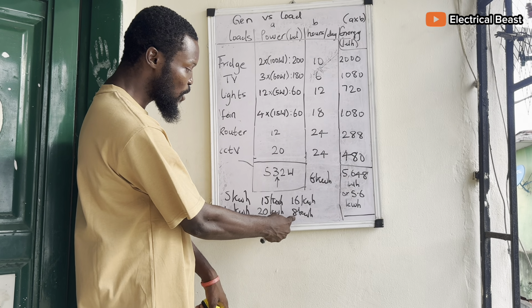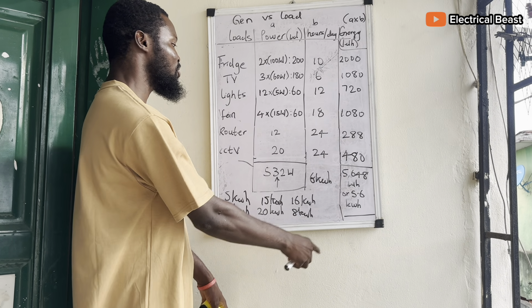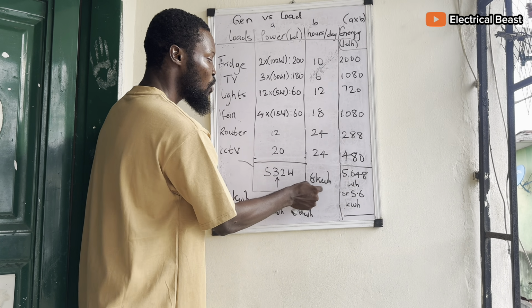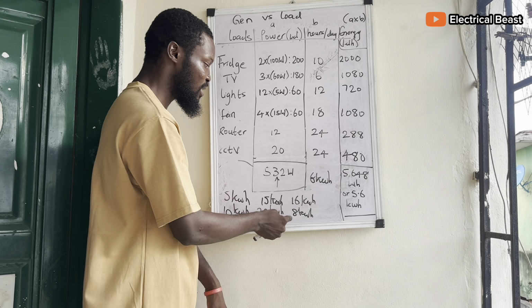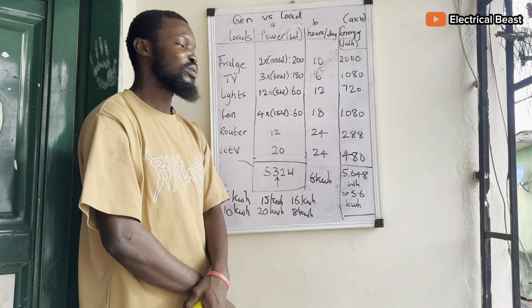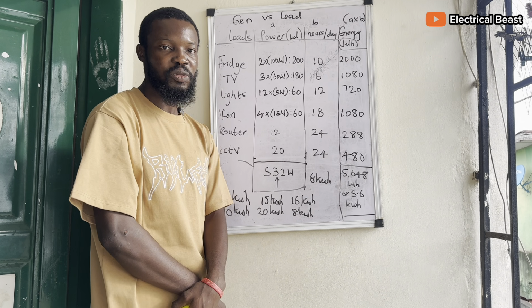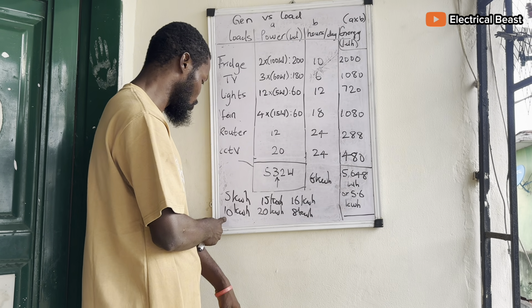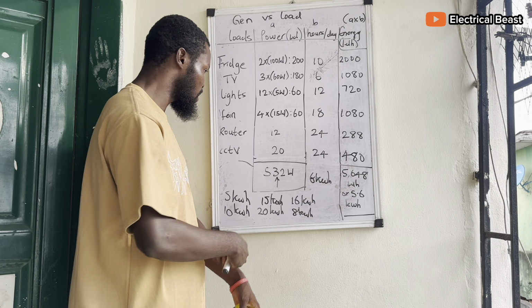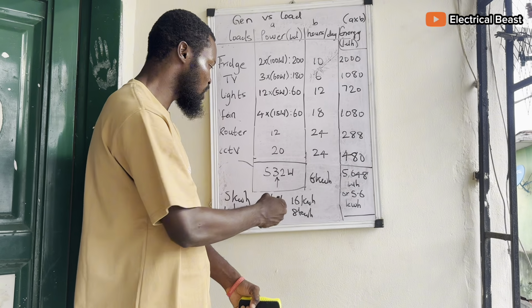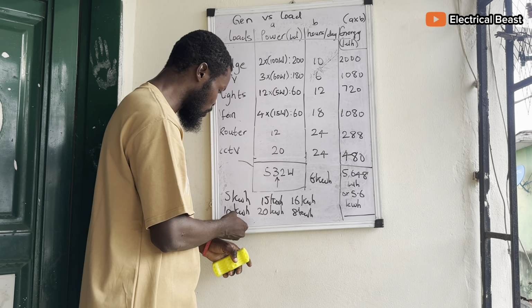So when you have 8 kilowatts and you want to use 8 kilowatts for 6 kilowatt daily energy consumption, and it is 80% depth of discharge, you know that you'll be having less than 8 kilowatts. It's not going to be enough. So assuming it's 10 kilowatts we're going for, we have 80% depth of discharge, then we can use 8 kilowatts. Okay, so we are going for 10 kilowatts.